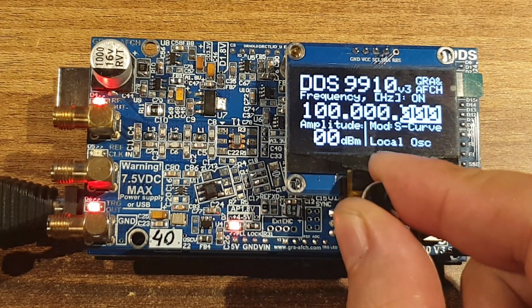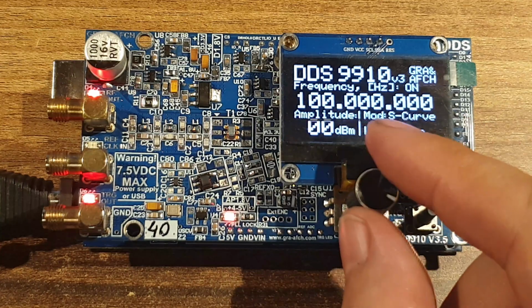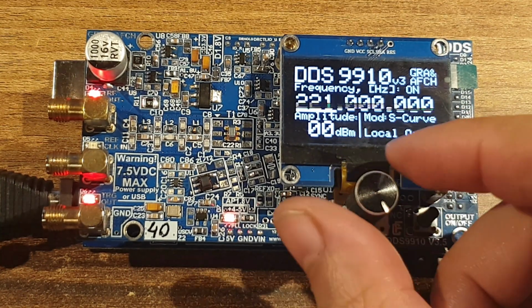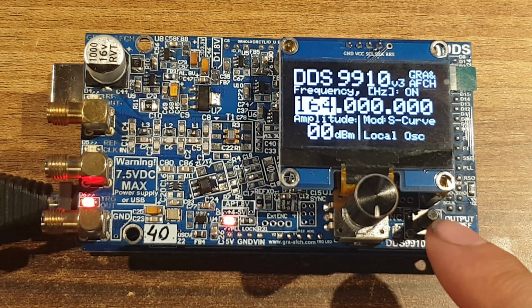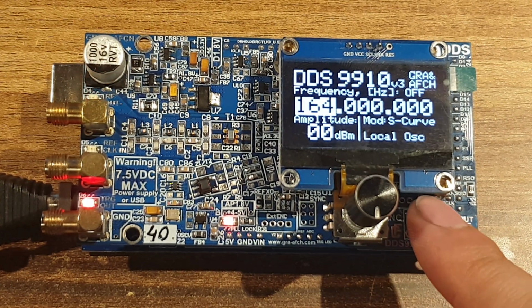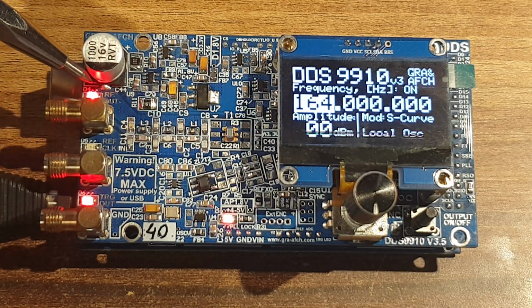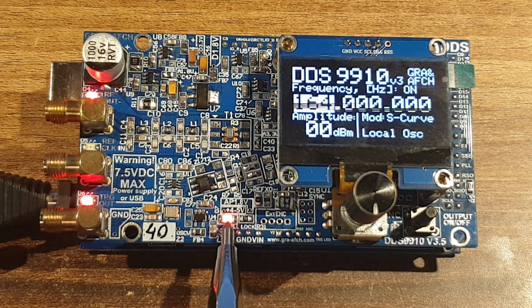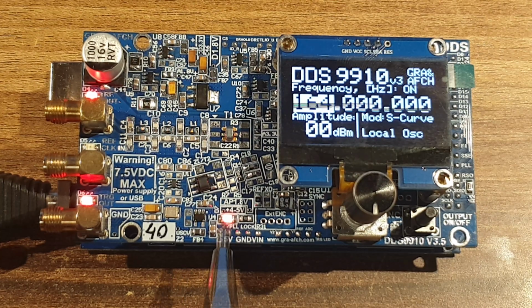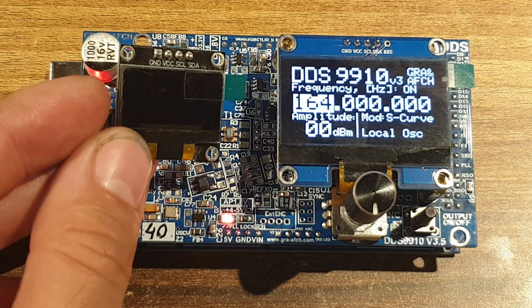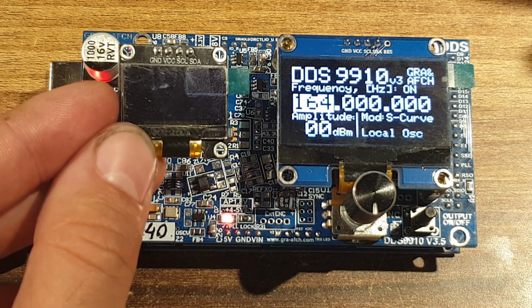Menu navigation has been upgraded. Buttons have been replaced with an encoder for easier control. A physical button has been added to toggle the RF output on and off. LED indicators have been introduced for each SMA connector, along with a separate indicator for PLL lock status. Support for a larger 1.54-inch display for users with impaired vision. The 0.96-inch display remains available.